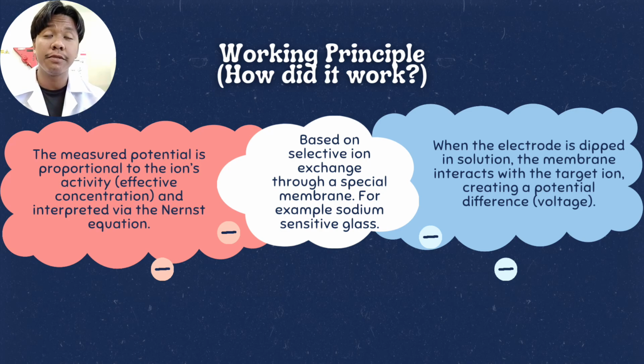So, for the working principle, how does it work? The measured potential is proportional to the ion's activity, which is the effective concentration, and is interpreted via the Nernst equation. It is based on selective ion exchange through a special membrane, for example, sodium sensitive glass. When the electrode is dipped in a solution, the membrane interacts with the target ion, creating a potential difference, which is a voltage.